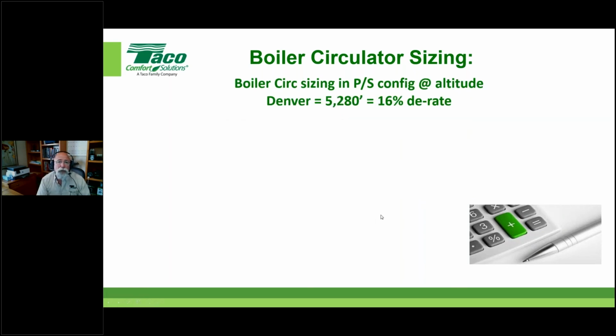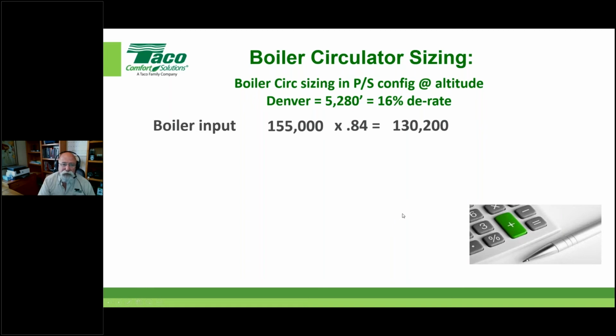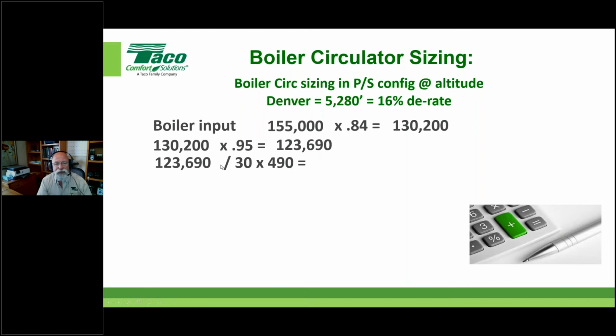Okay. Here's one with altitude. Some people say, well, altitude, again, if you get something from the manufacturer, you go through the steps of proving that you're getting a certain amount of BTUs per cubic foot of gas, then by all means. But like I said, if you get something from the people that supply that gas that say, hey, you're going to take a derate, then be sure to derate that first. Your derate comes off of that. Then that 155 becomes a 130-200, and then you take your efficiency off of it, which gives you a maximum net output. And that's what you size the pump on.